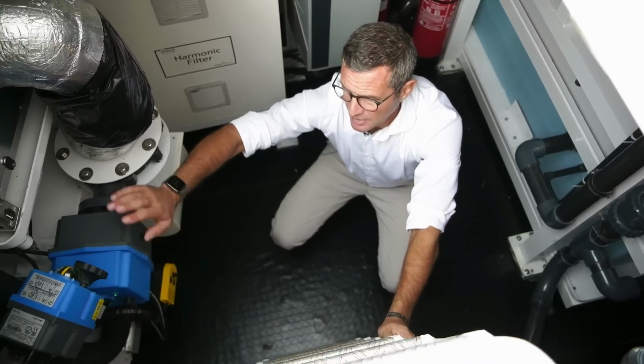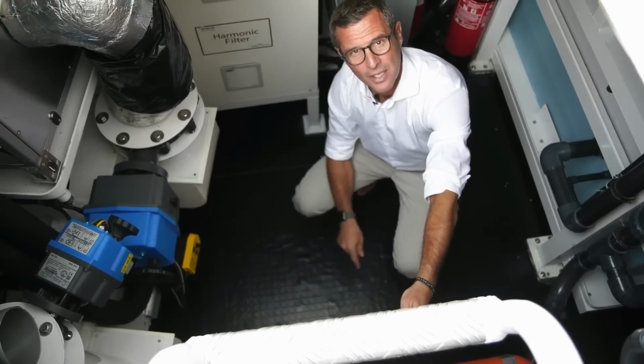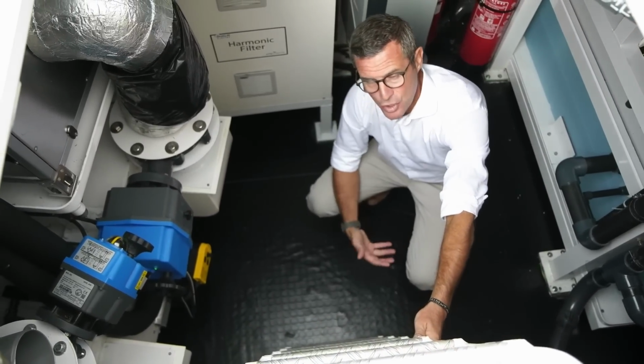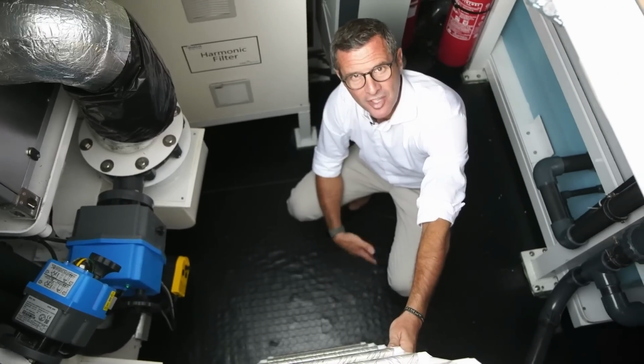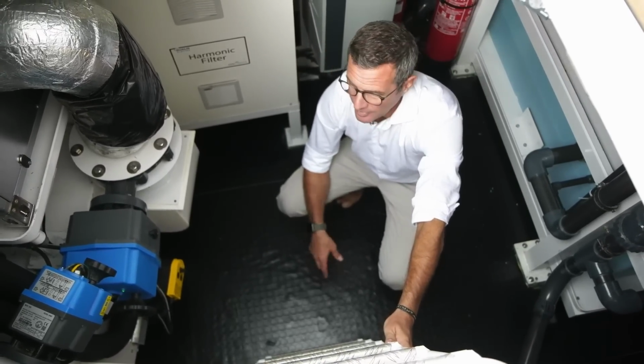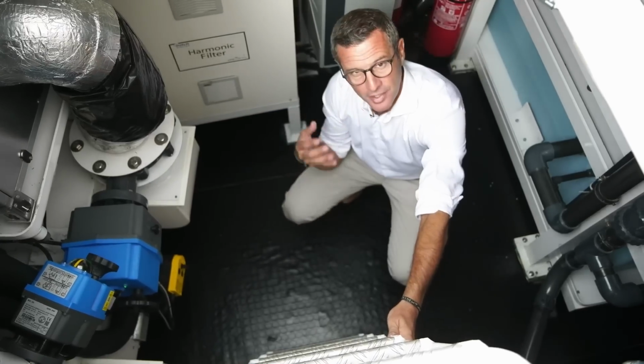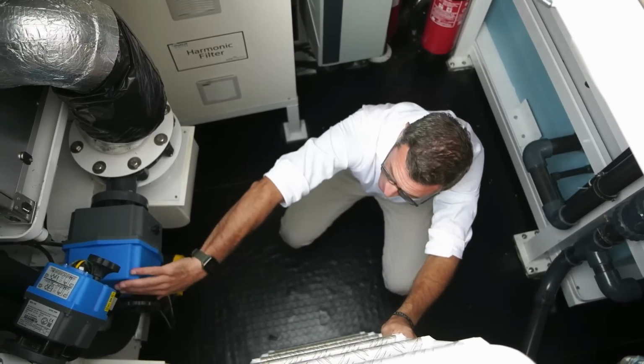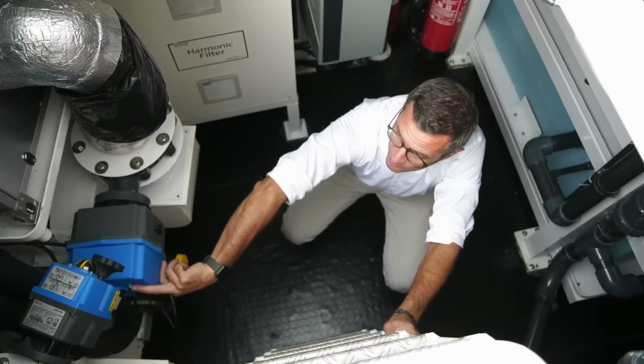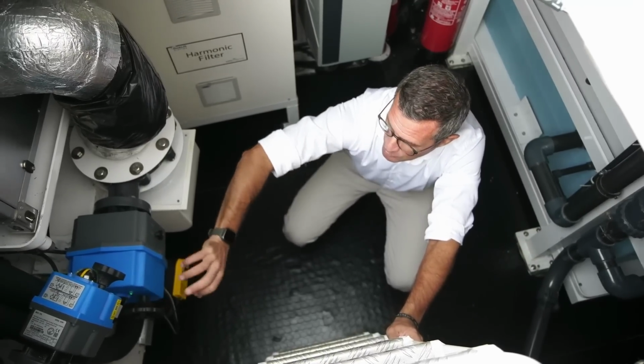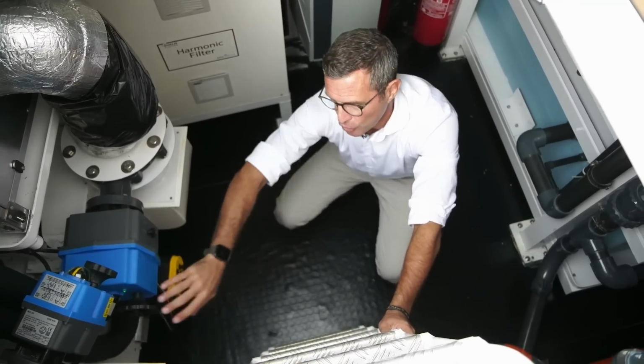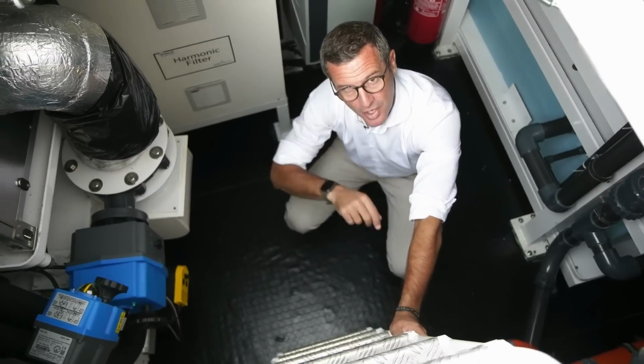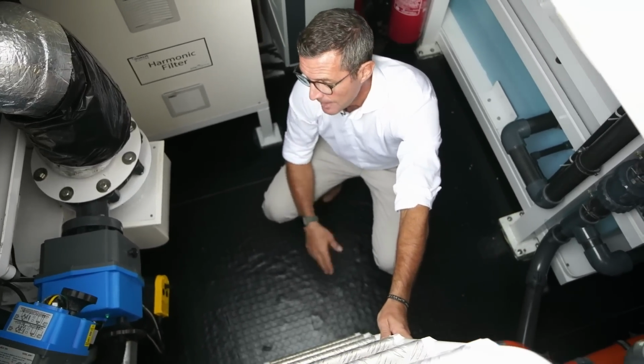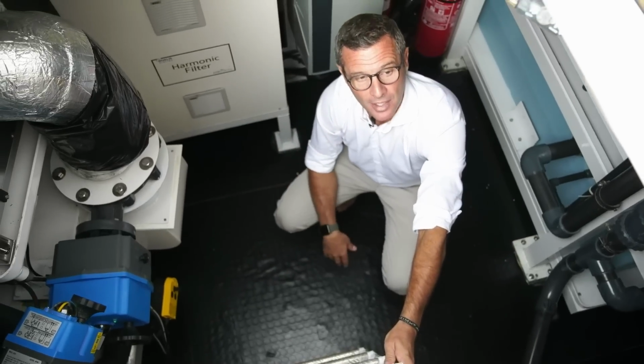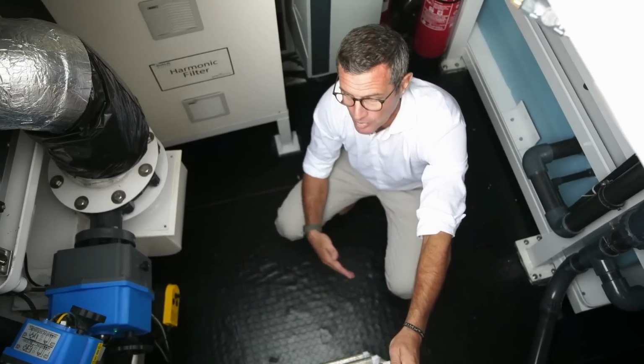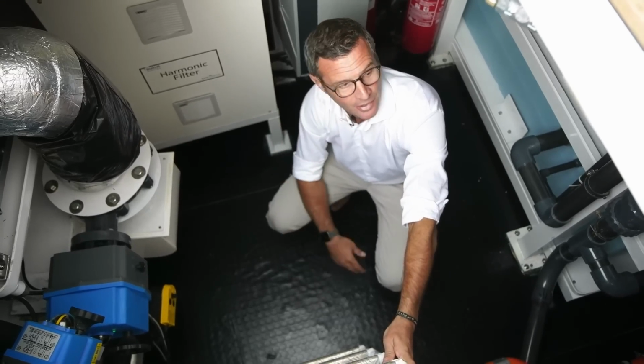These are your valves in case of a fire. Obviously you want to remove any source of air that would feed the fire. All these valves are integrated into the firefighting system. They're electrically operated - you can see a green LED light here showing the valve is open, and you can control them manually through this lever or electronically. We'll see how later on. They shut off automatically or manually in case of fire, to cut the air throughout the boat.